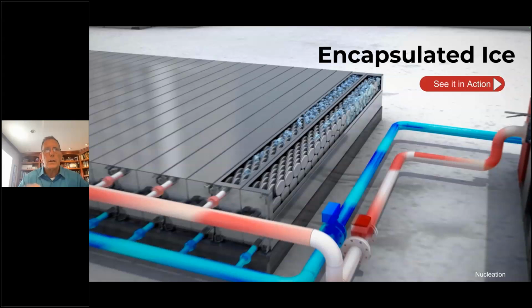Then basically flowing the water through, whether you're on the charge or discharge timeframe. If we're charging it, we simply run cold water at around 26 degrees, a glycol water mix, through that shell. Inside each of those sealed capsules, it freezes, and then we let it sit. When it's discharge time, we turn on the pumps, flow the water backwards through there, and now we're providing cold water back to the chilled water system or the loop inside the building.